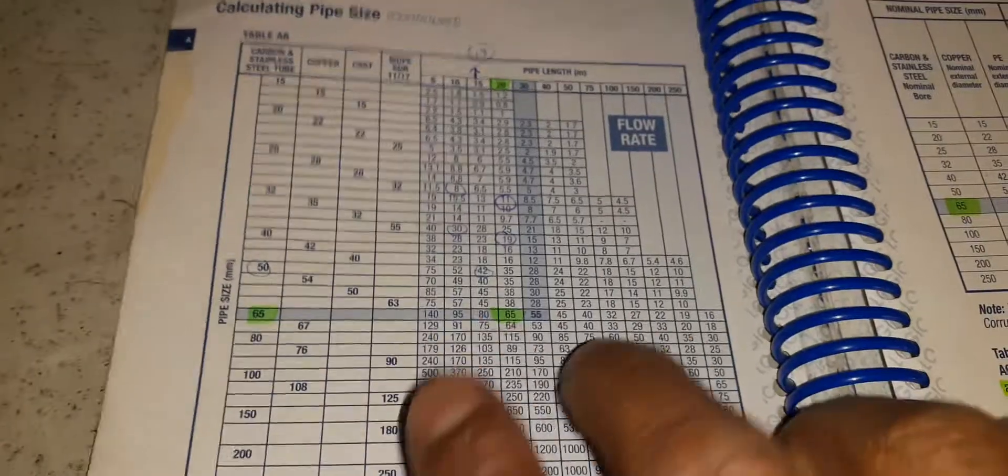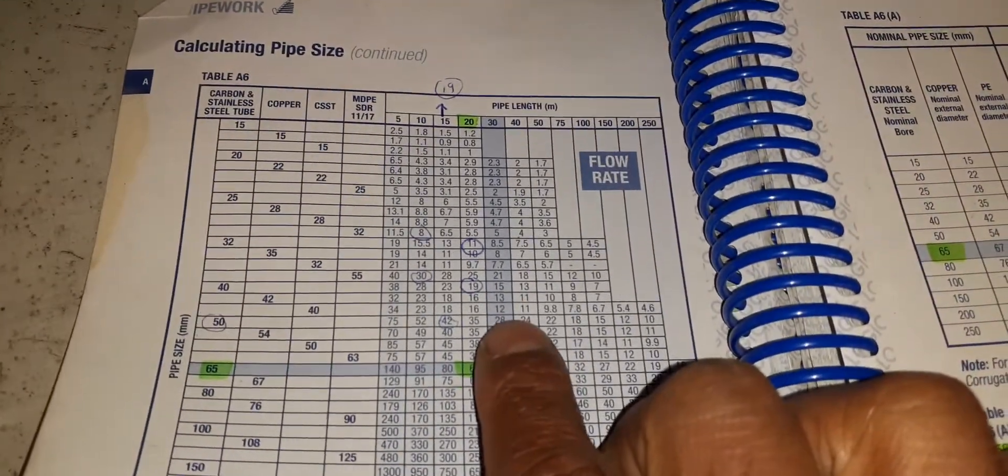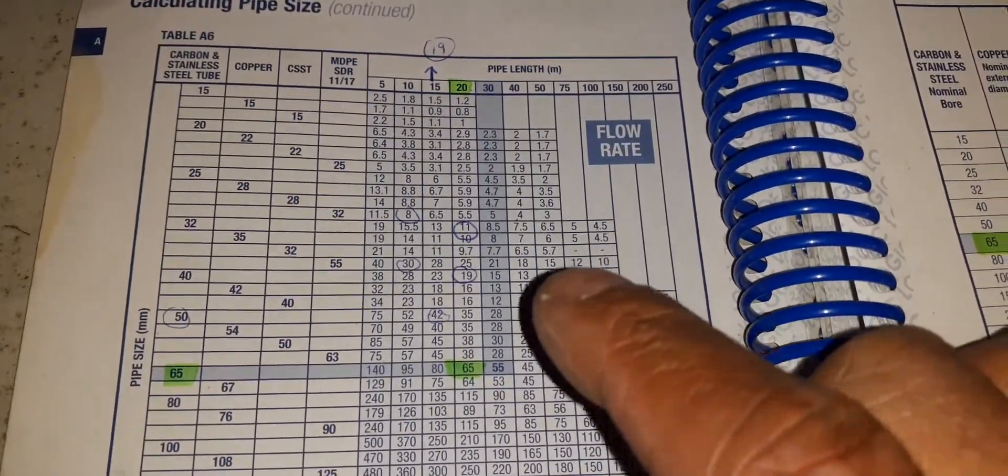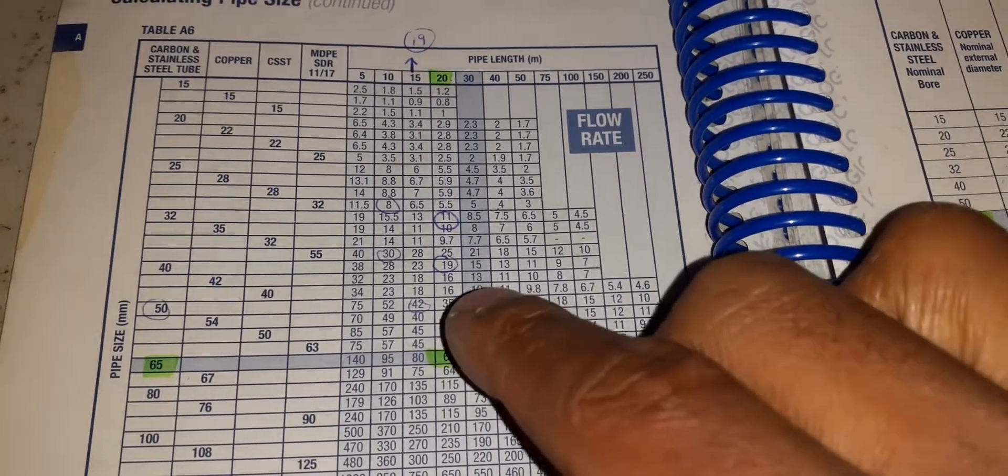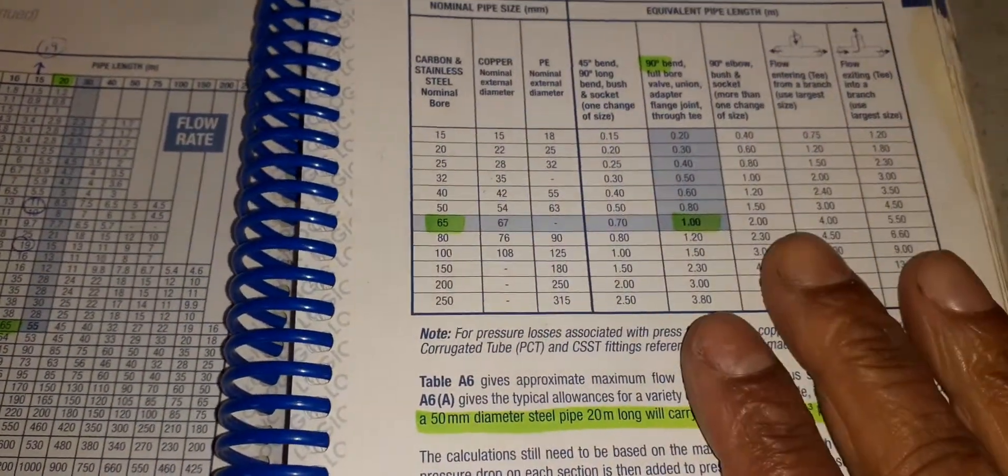So that's what we have to add on to our pipe run. Say for instance we had 10 elbows - we no longer have 18 meters of pipework anymore, we would have 28 meters of pipework because that's what the restriction is causing.